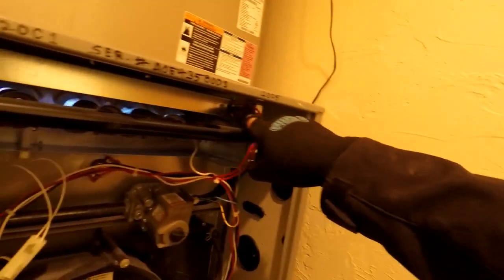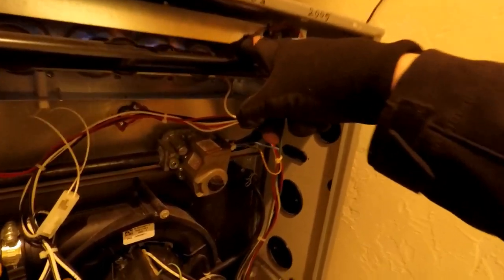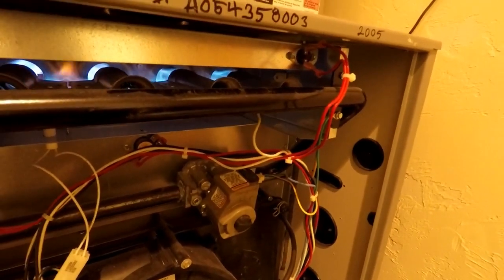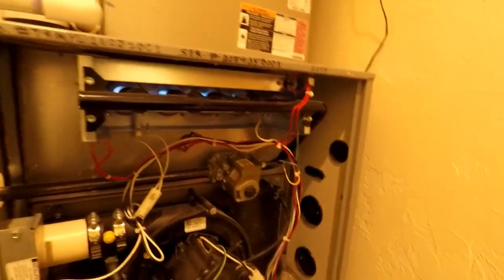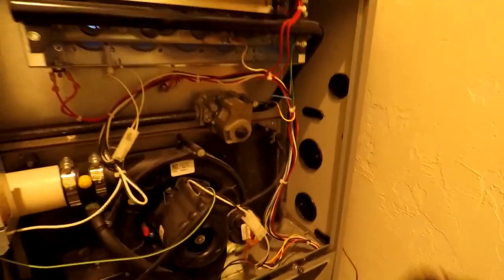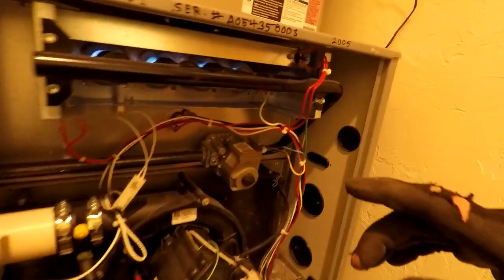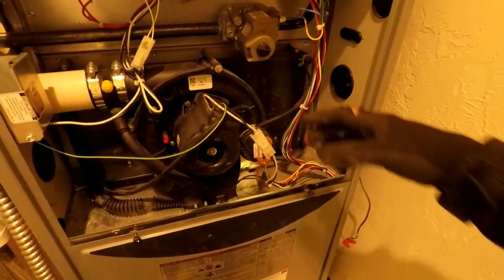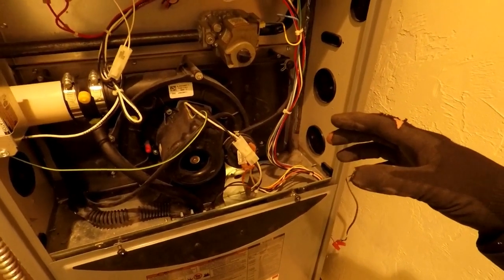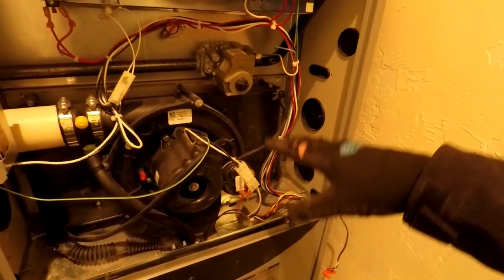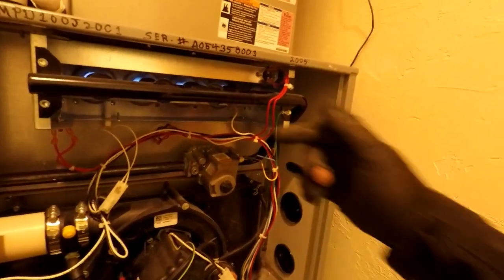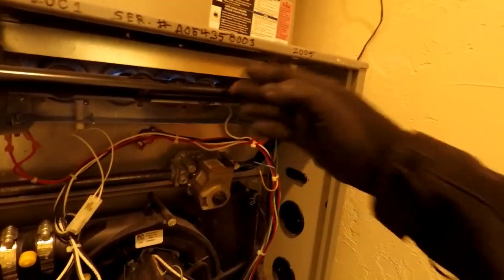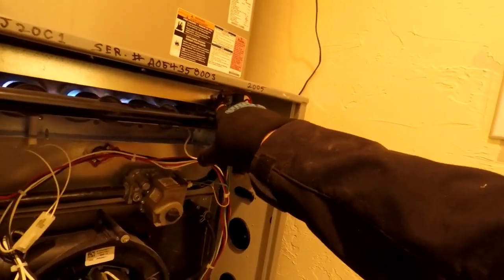Now this was the one that was tripped, so that would be the side that was probably rolling out. And if the inside of that secondary heat exchanger is plugging up, as it runs and more water comes down the exhaust and fills the secondary heat exchanger, if it's plugging up, that could be enough to push that flame back into this firebox, which would get this switch hot and cause a tripped rollout switch like what we had. So, all right, I'm going to amp this motor and keep an eye on that.